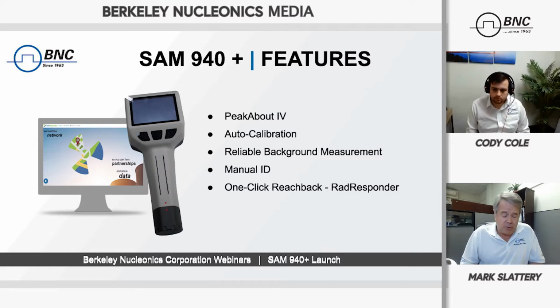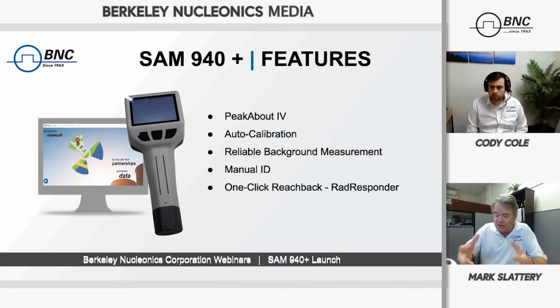Auto calibration, of course, that's always been a feature. Same with the SAM 940 and the 940 Plus. The 940 Plus can do it without the potassium chloride contained in the ring on the detector. Reliable background measurement. Well, of course, that's necessary, whatever RID you're doing. You need the background reference because you are surrounded by radiation no matter where you are. There's always some. And the idea is let's find out what we can expect in the area where we are, and sort of capture that. It's almost like taking a picture of it and storing it in your memory.